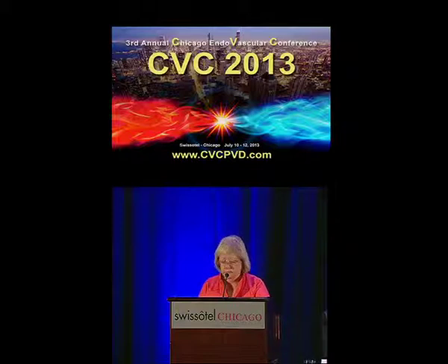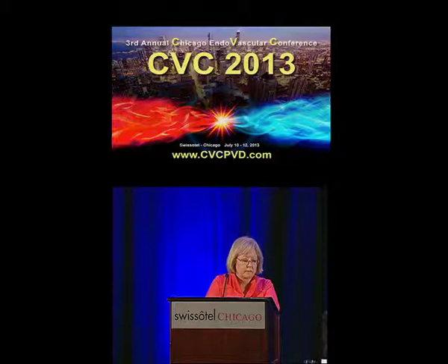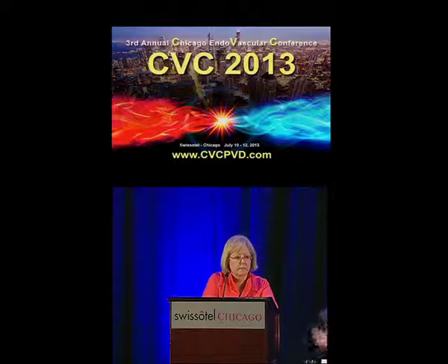Again, I don't think there's any difference, well, I'll be specific. If you use Boston Scientific, it supposedly has better image quality, more crispness, but it is a single crystal that rotates. You have to have a housing unit and put it up on the patient and then run the catheter back and forth. I personally have had problems with that because we're imaging over longer areas or around bends, and if that catheter kinks or whatever, it will break in that rotational housing unit, and I've gone through more catheters that way, which is expensive.